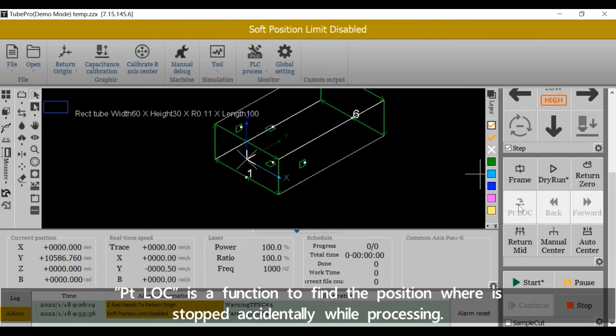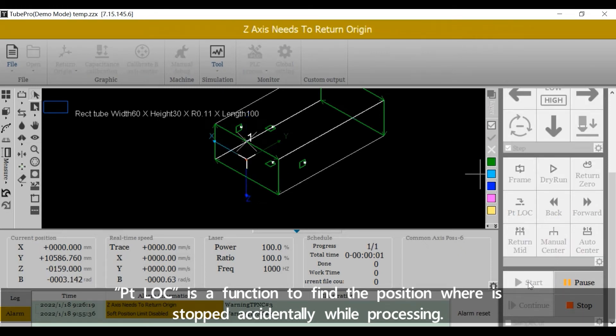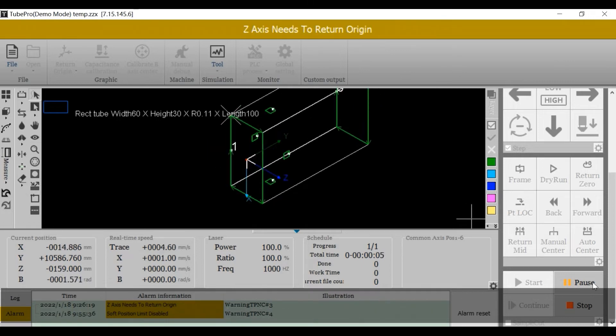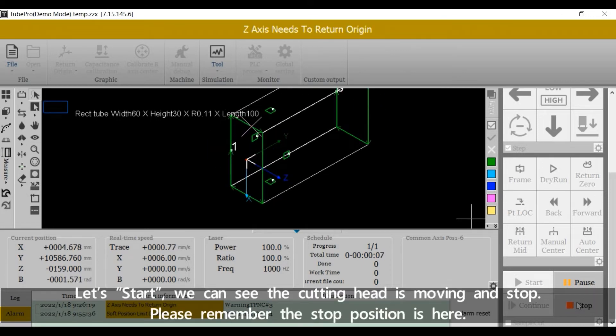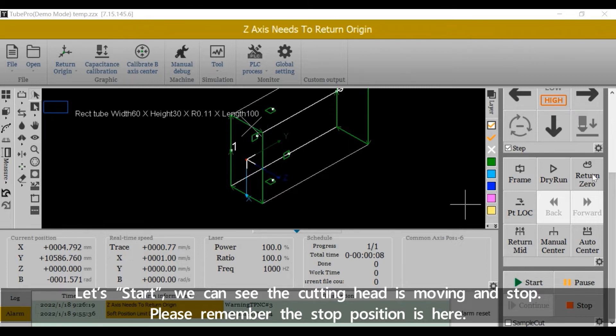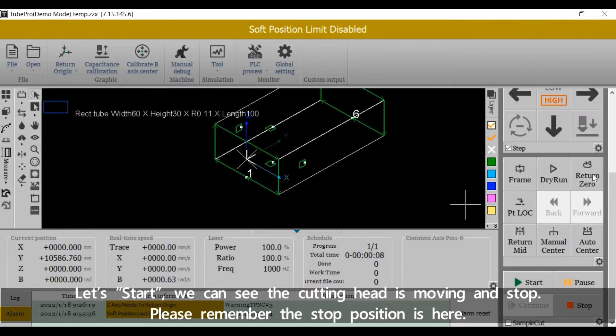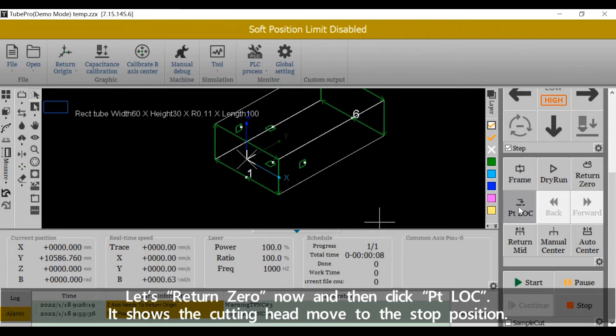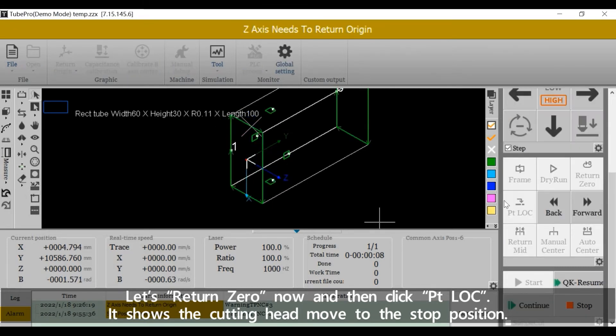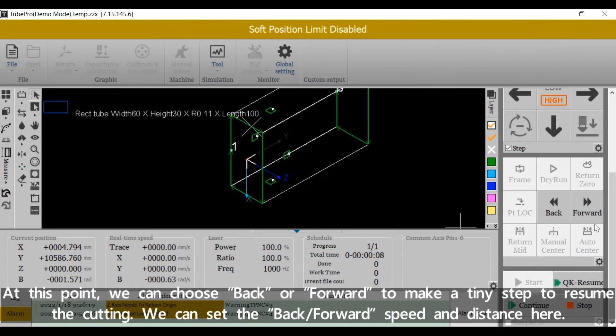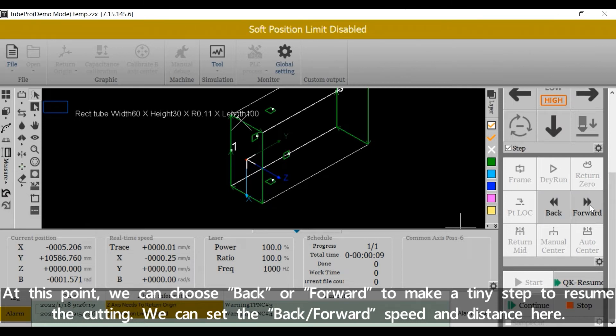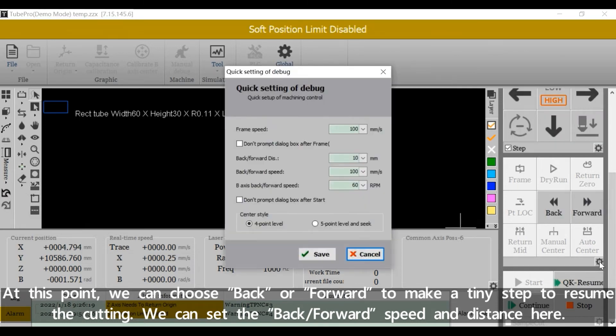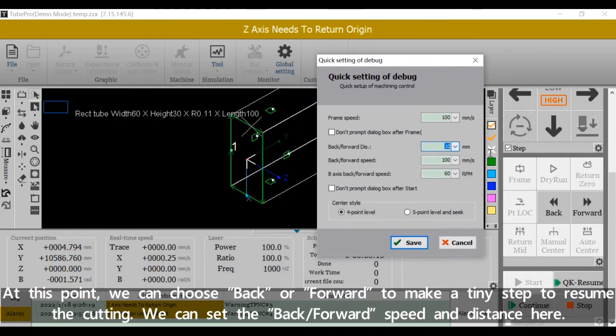Pt LOC is a function to find the position where it stopped accidentally while processing. Let's start. We can see the cutting head is moving, and stop. Please remember the stop position is here. Let's return 0 now and then click Pt LOC. It shows the cutting head moved to the stop position. At this point, we can choose back or forward to make a tiny step to resume the cutting. We can set the back forward speed and distance here.